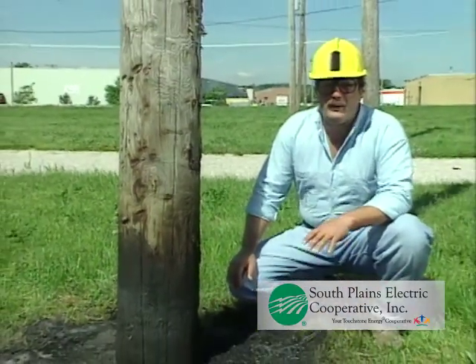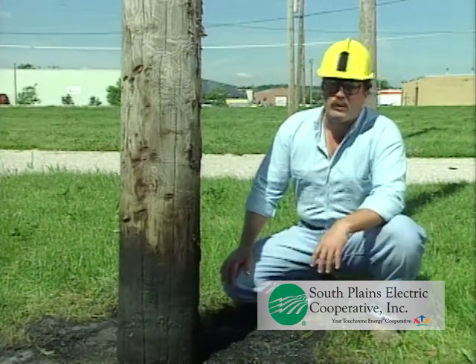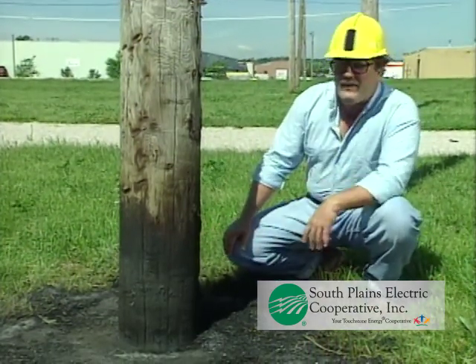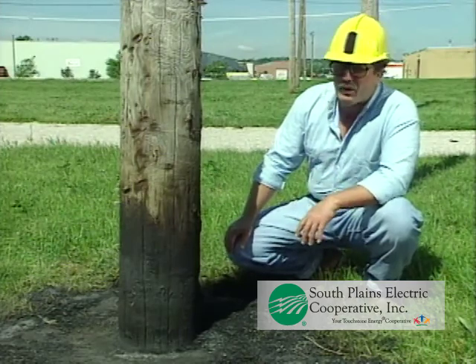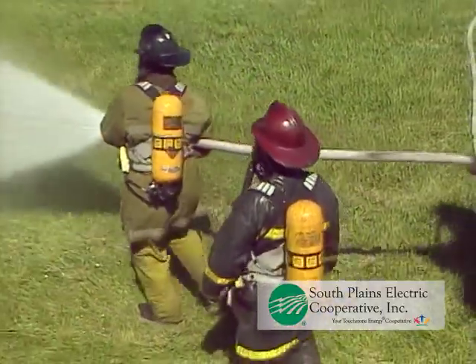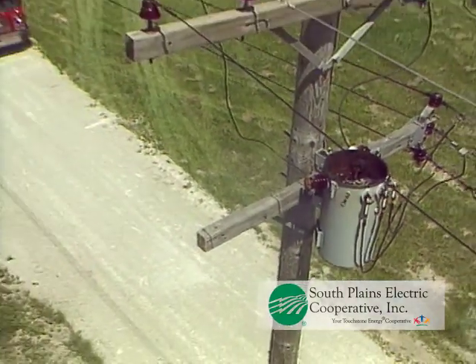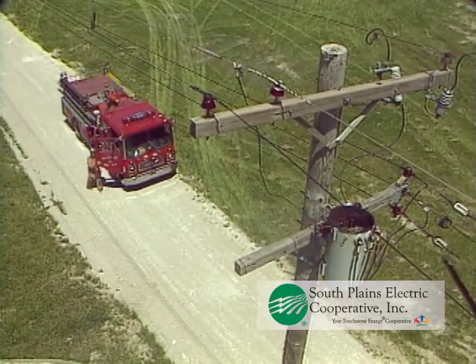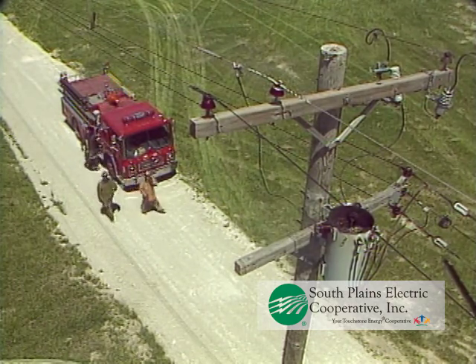When a grass or small brush fire is burning under power lines or around the base of poles, use standard firefighting practices to extinguish the fire. If there's deep char around the base of the poles, notify the electric utility, because they're going to want to inspect the poles for possible replacement. If a downed wire is involved in the fire, use a spray stream to keep the fire in check and protect the surrounding area — never use a straight or solid stream. If the fire is near the top of the pole or in pole-mounted equipment such as transformers, oil switchgear, or capacitors, and it appears that the fire will not endanger life or property, let it burn and quickly notify the electrical utility.